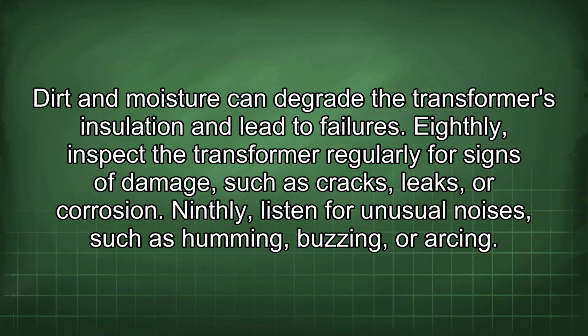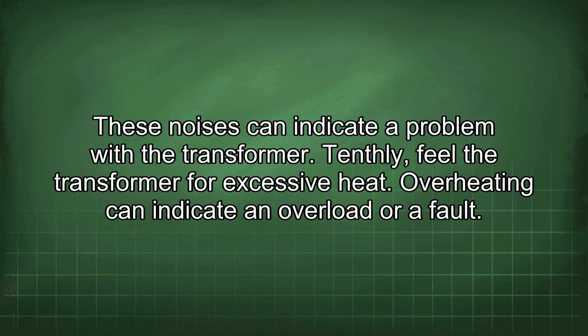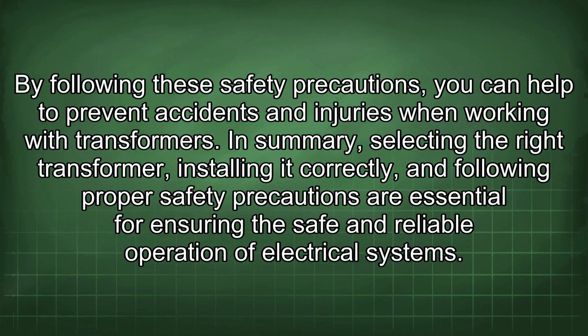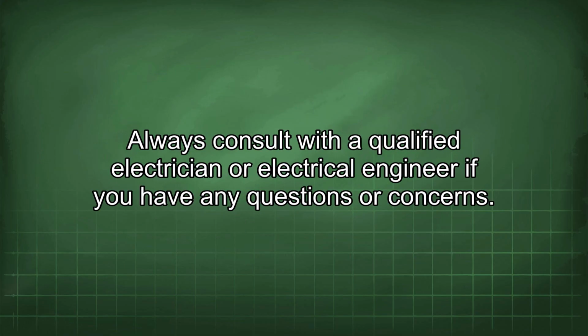Eighthly, inspect the transformer regularly for signs of damage such as cracks, leaks, or corrosion. Ninthly, listen for unusual noises such as humming, buzzing, or arcing. These noises can indicate a problem with the transformer. Tenthly, feel the transformer for excessive heat. Overheating can indicate an overload or a fault. By following these safety precautions, you can help to prevent accidents and injuries when working with transformers. In summary, selecting the right transformer, installing it correctly, and following proper safety precautions are essential for ensuring the safe and reliable operation of electrical systems. Always consult with a qualified electrician or electrical engineer if you have any questions or concerns.